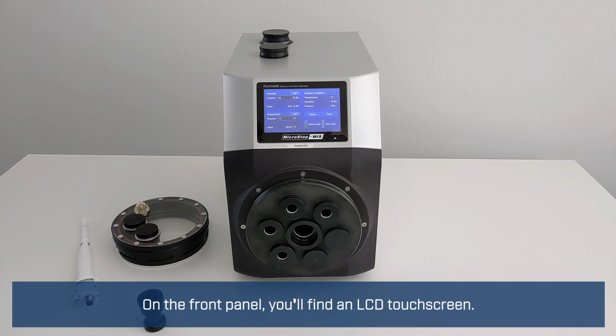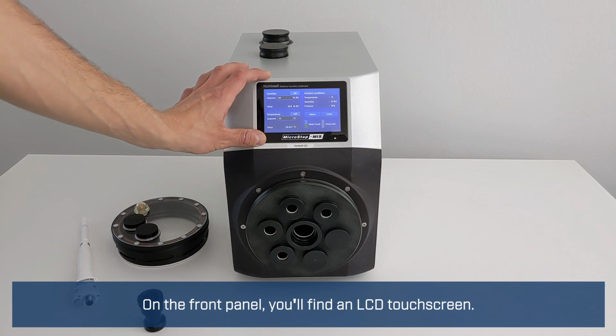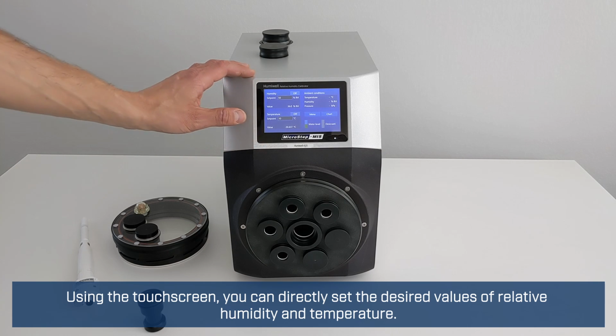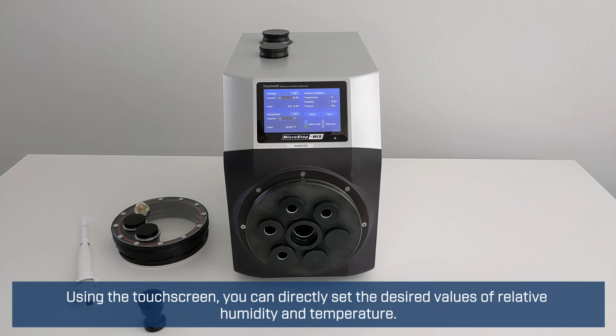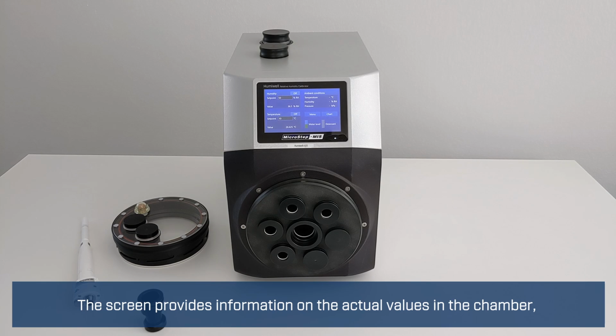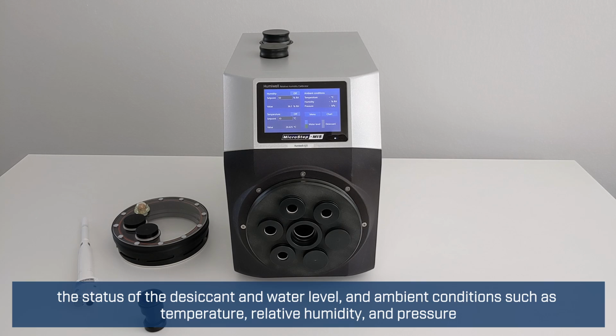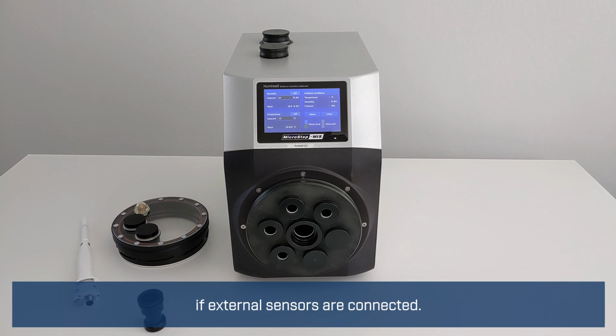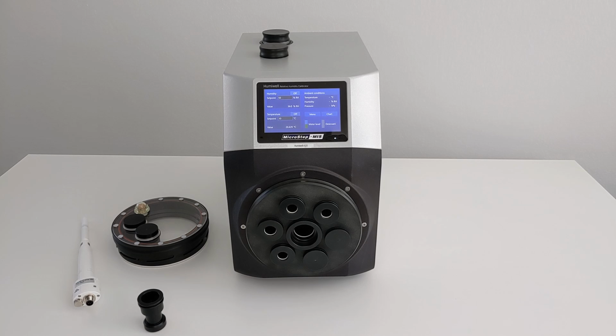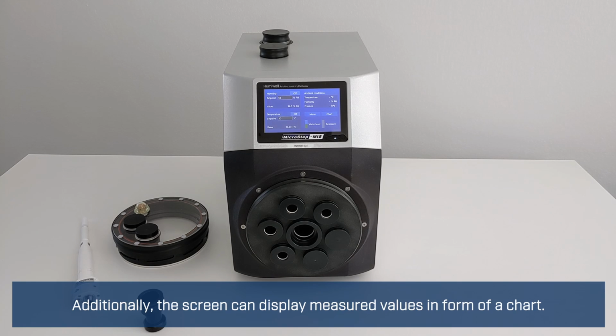On the front panel, you'll find an LCD touchscreen. Using the touchscreen, you can directly set the desired values of relative humidity and temperature. The screen provides information on the actual values in the chamber, the status of the desiccant and water level, and ambient conditions such as temperature, relative humidity, and pressure if external sensors are connected. Additionally, the screen can display measured values in graphical form.